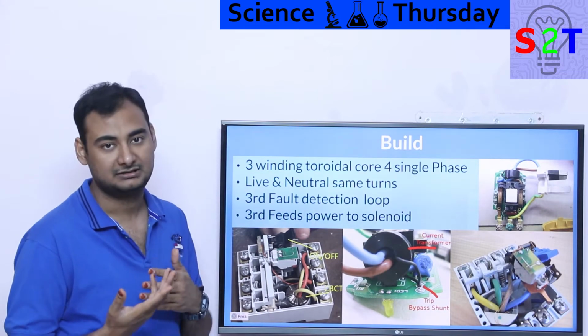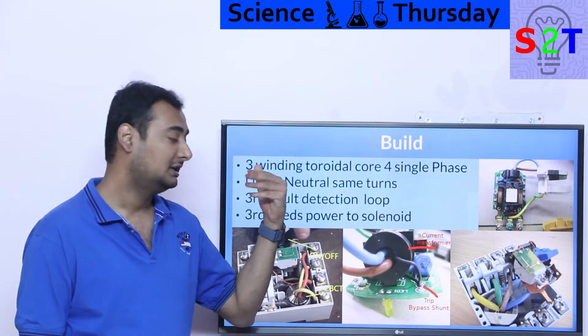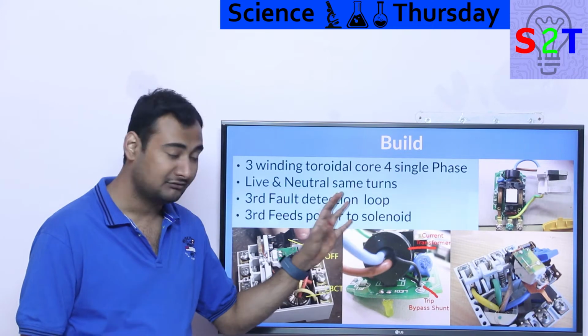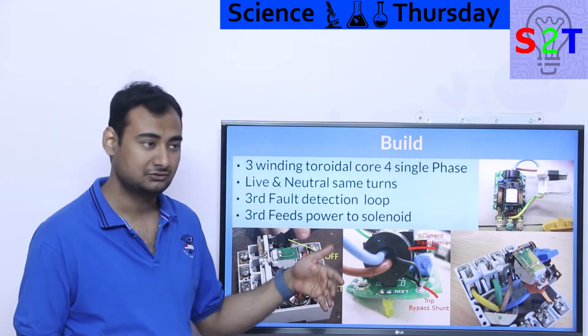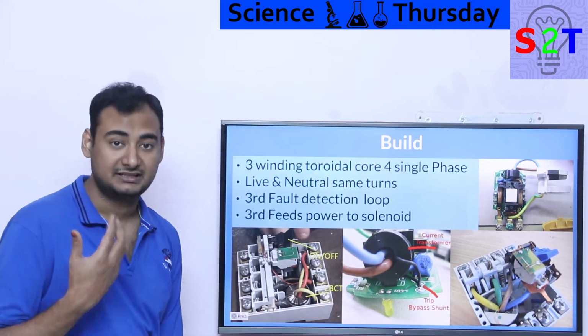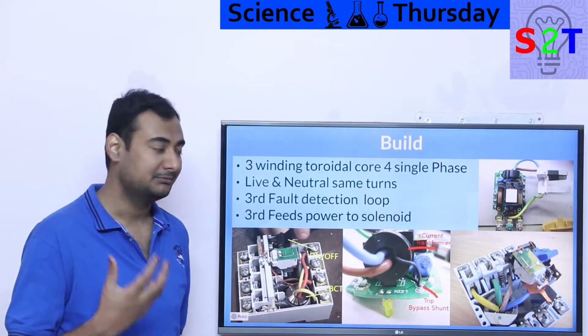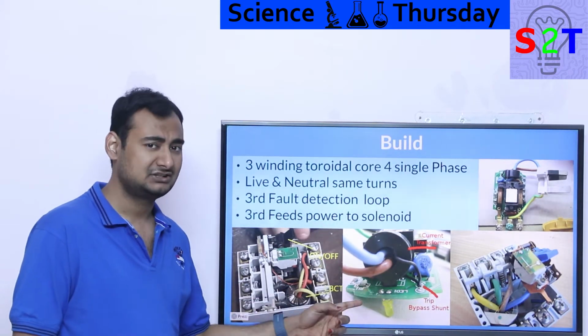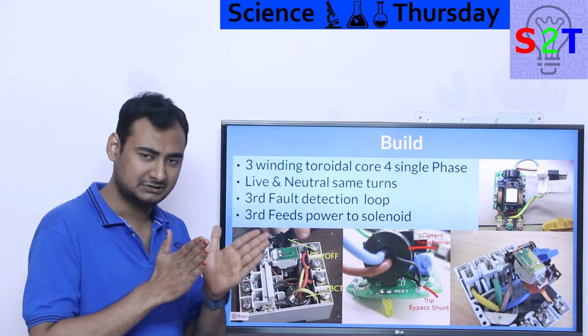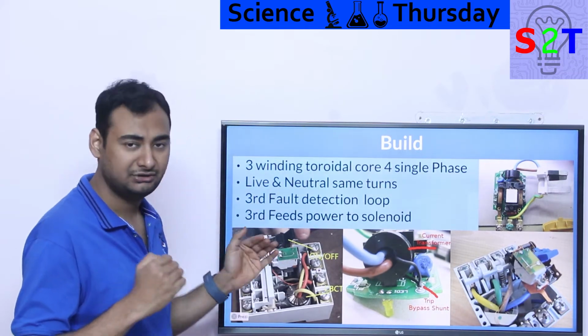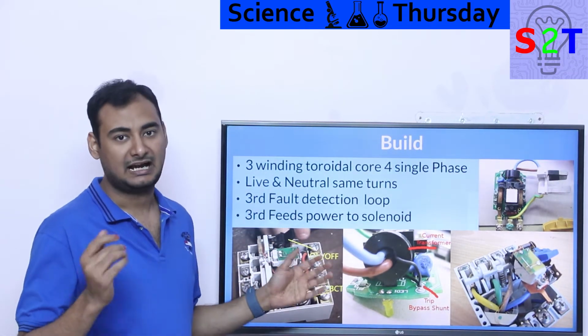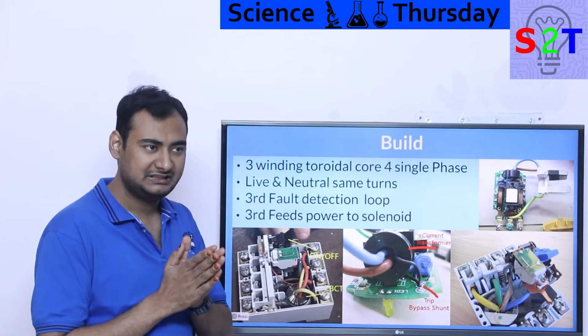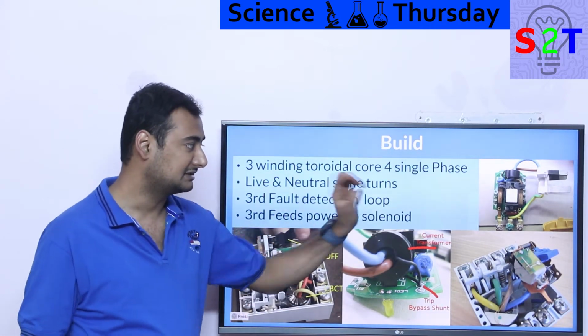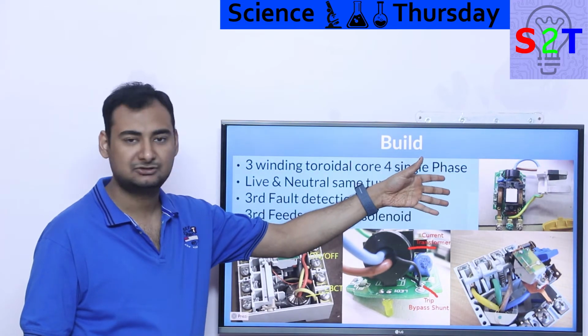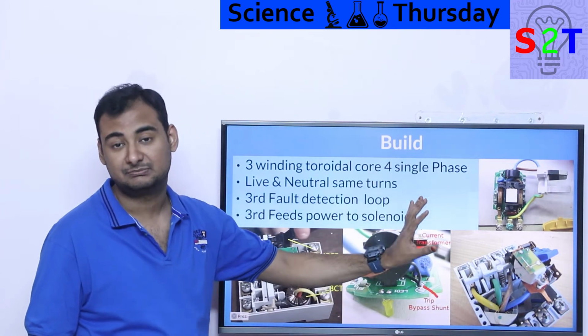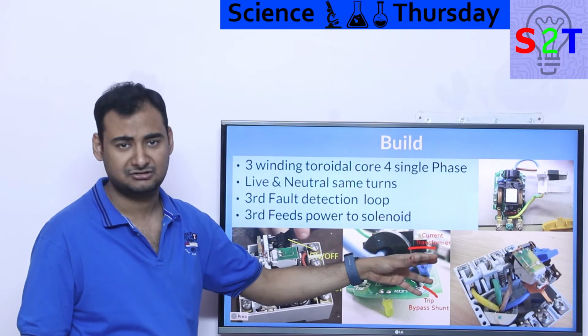The sensing system would be designed in such a way that it can extract the energy that it needs to fire itself. Depending on how much energy is needed to trigger the system, depending on how sensitive they want to make it. Again, if you are putting this on a distribution box, you don't want this to be as sensitive as possible. You do want some leeway because things happen. You don't want this puppy to keep tripping randomly overnight. So if it is directly on your plug, you may want that to be 30 milliampere, but something that is on your main circuit breaker, you may want to be at around 100 milliampere.